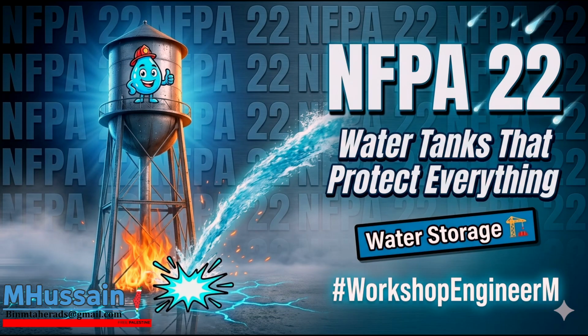Let's break that down, because the variables are tricky. If the air pressure drops to zero while there is still, say, 500 gallons of water sitting in the tank, that water is dead weight. Completely dead weight. It will just sit in the basement while the roof burns. So how does an engineer physically calculate that initial pressure and volume requirement?